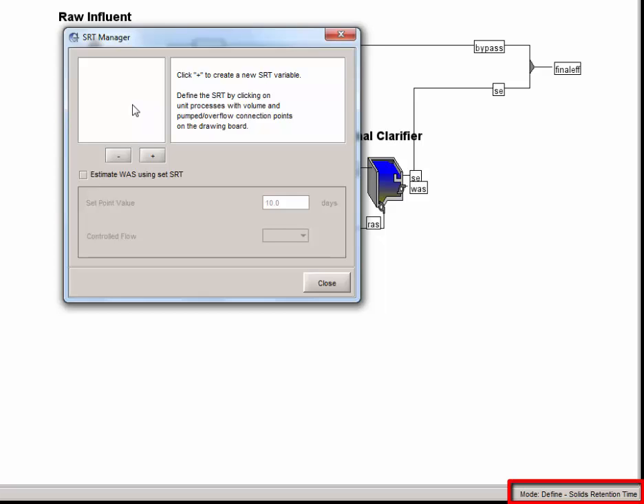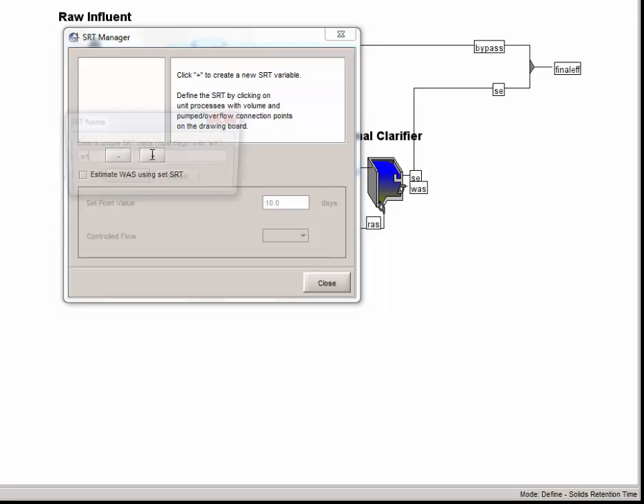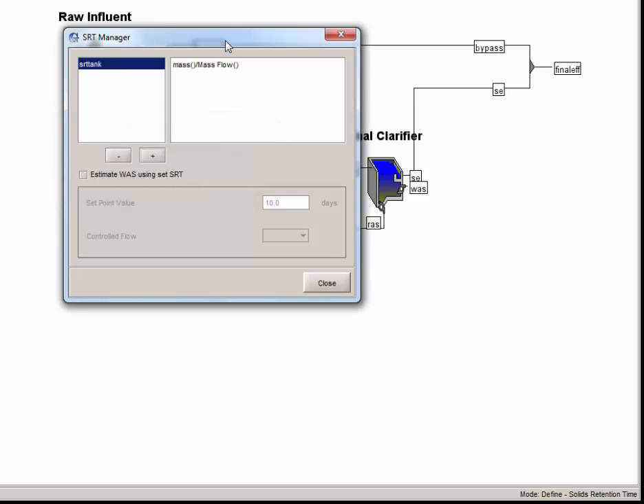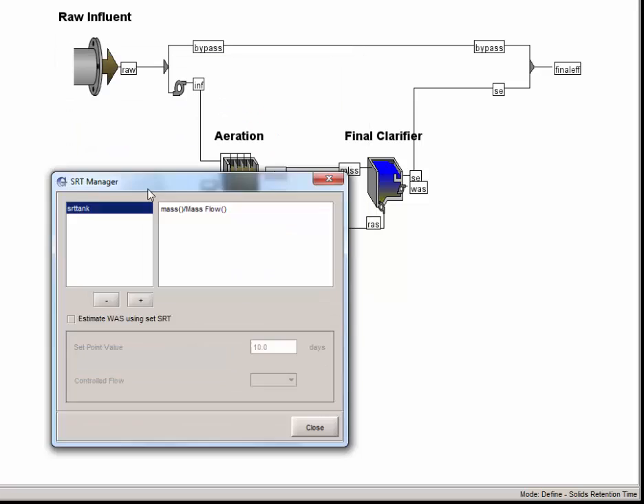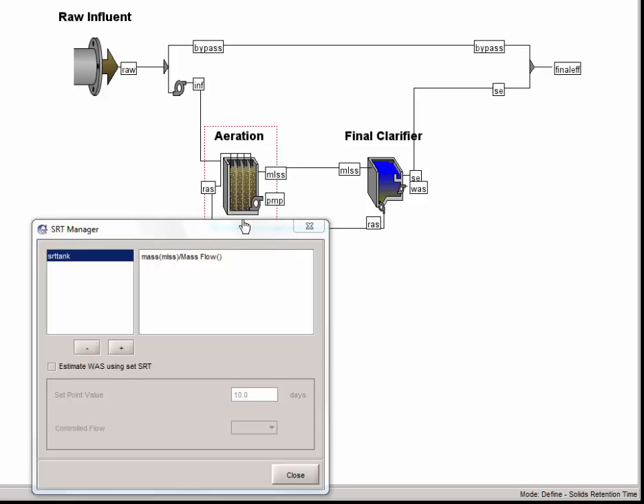This is the mode we need to be in to define the SRT equation. Click on the plus button below the left-hand window in the SRT manager menu. Enter a name for the SRT calculation, in this case SRT tank, and click OK. A new blank equation will be shown in the right-hand window. To begin defining the SRT equation, click the aeration tank and select all reactors within the plug flow tank to be added in the SRT equation. There are two parts to the equation. The numerator is the mass portion and includes things like the mass of solids held in each tank.